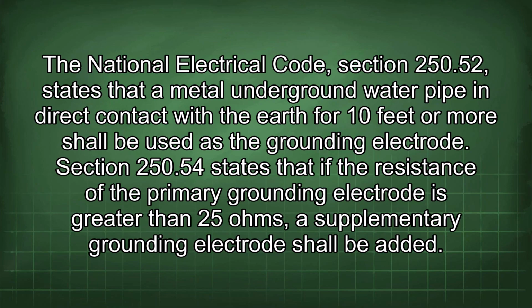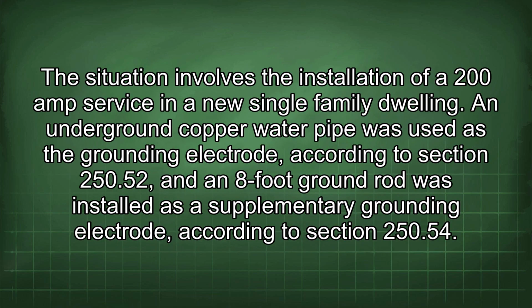The National Electrical Code, Section 250.52, states that a metal underground water pipe in direct contact with the earth for 10 feet or more shall be used as the grounding electrode. Section 250.54 states that if the resistance of the primary grounding electrode is greater than 25 ohms, a supplementary grounding electrode shall be added. The situation involves the installation of a 200 amp service in a new single-family dwelling.